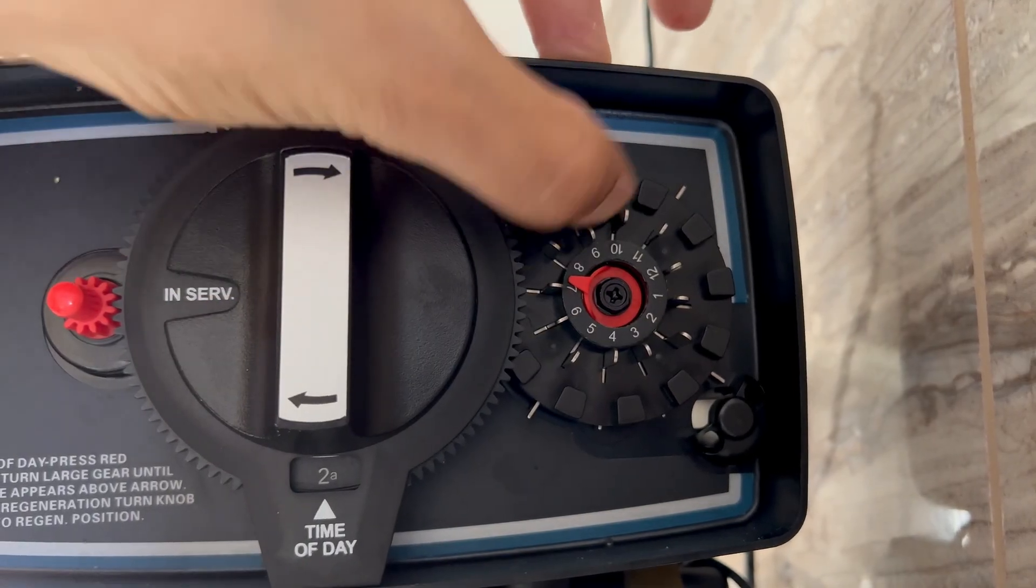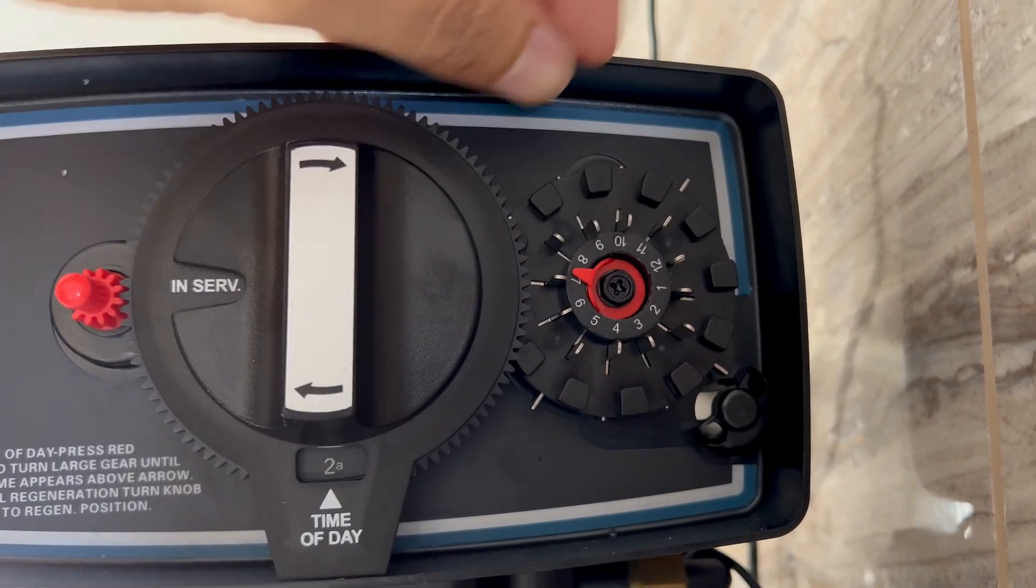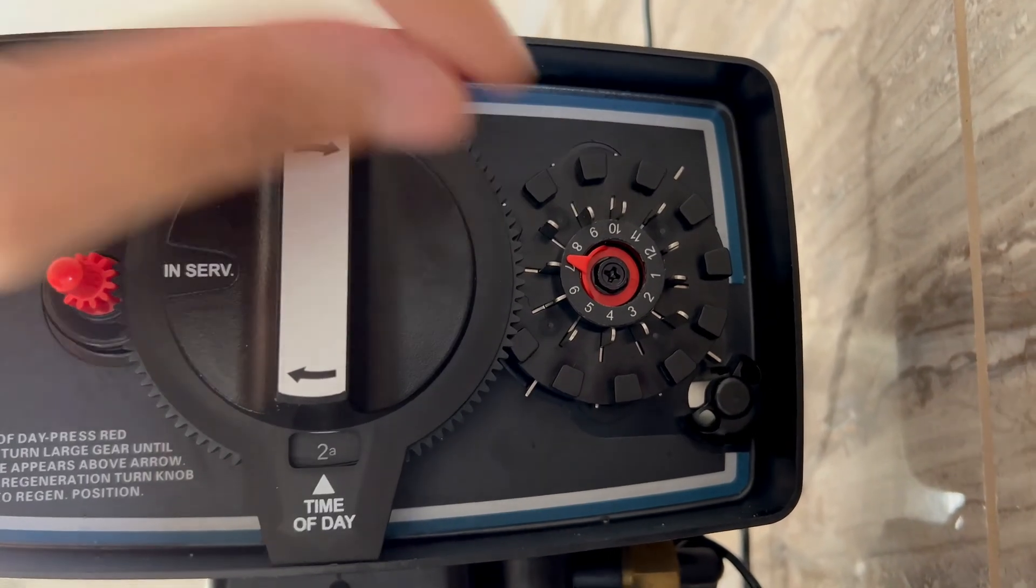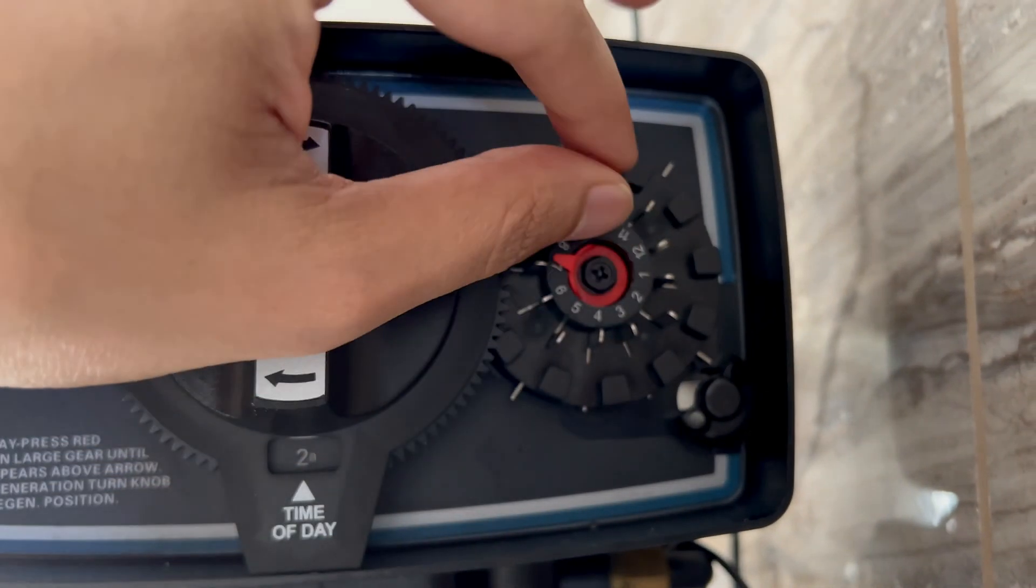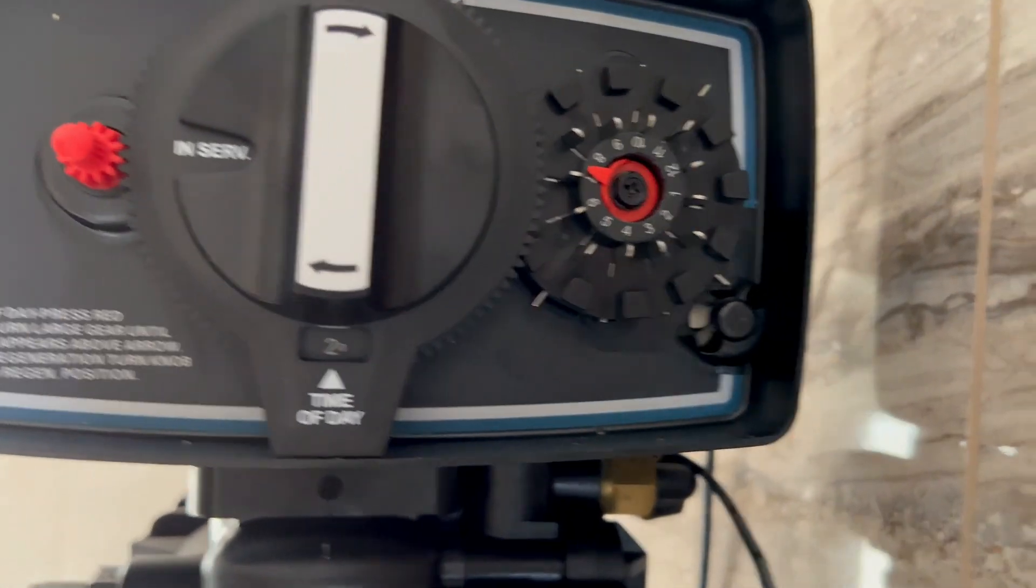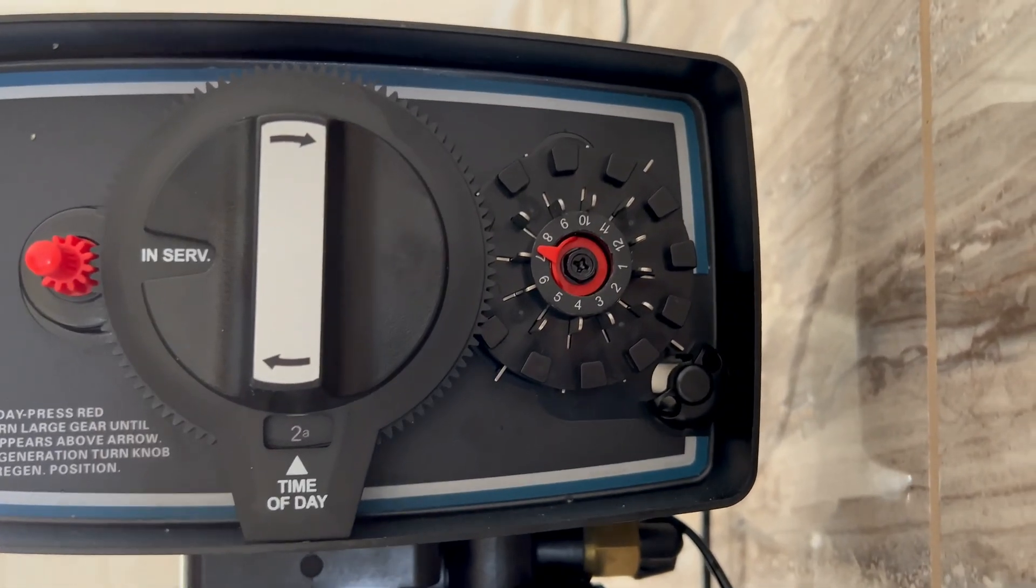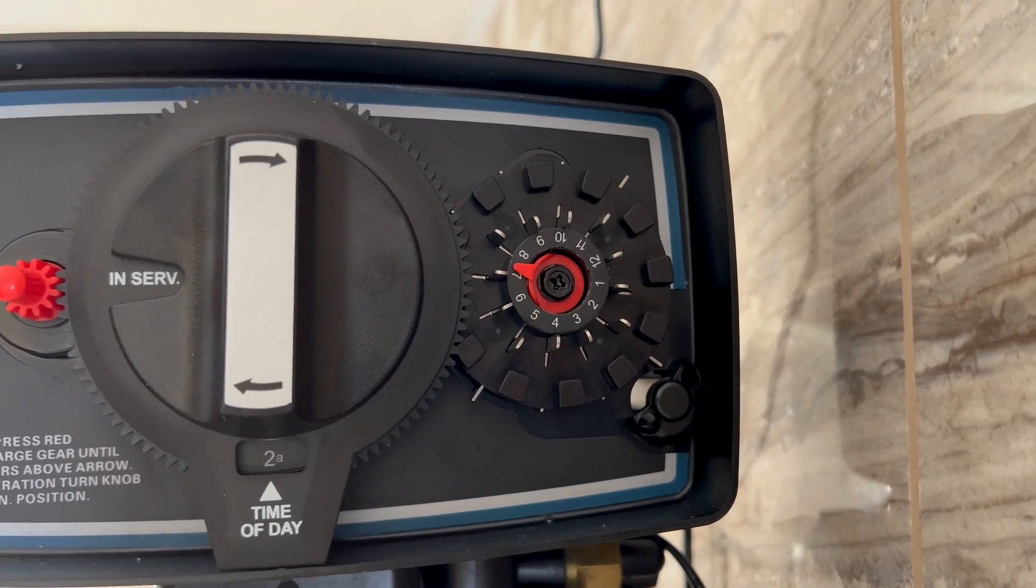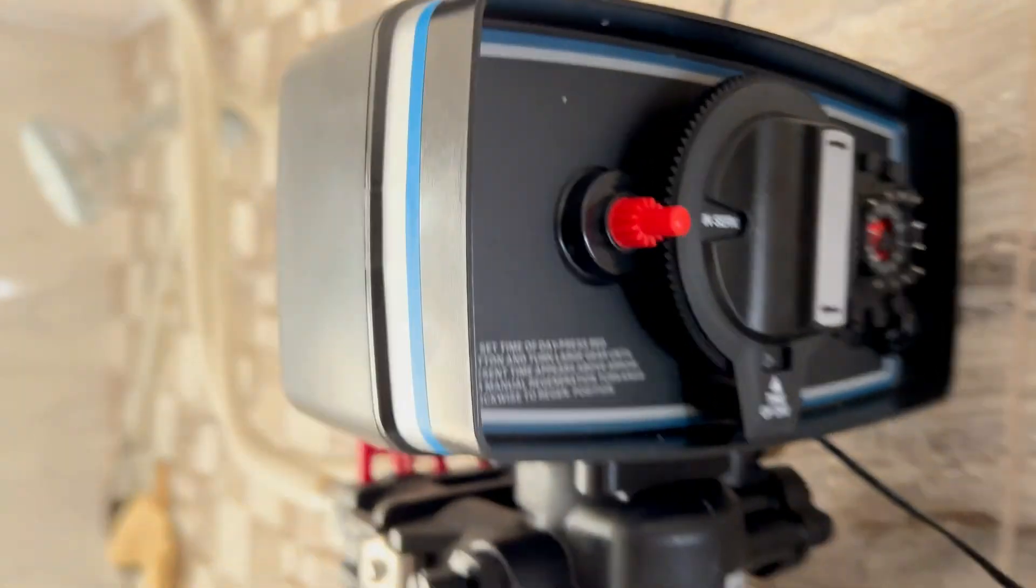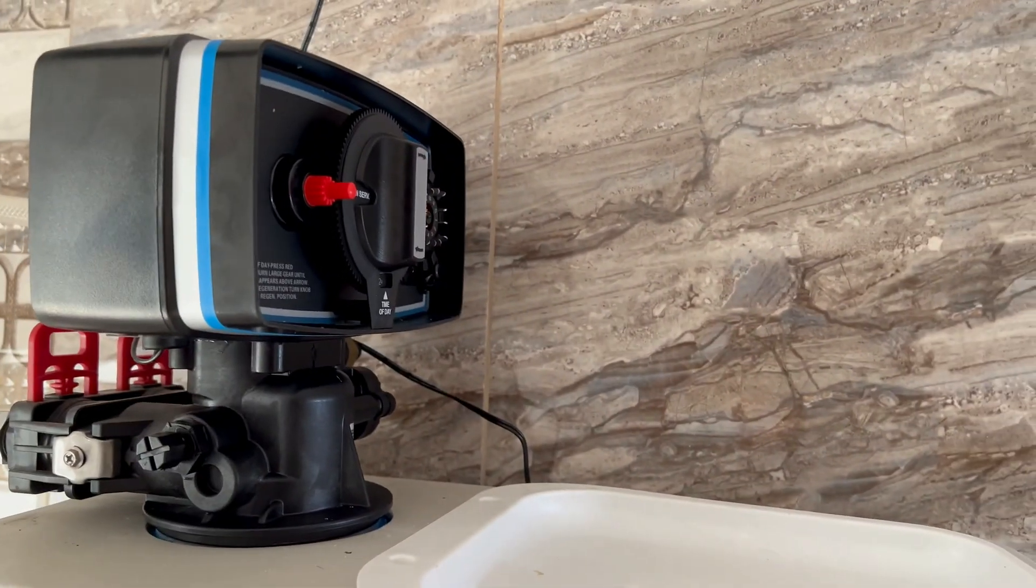The machine is designed to regenerate water at 2 a.m. based on its internal settings and it generally takes three and a half to four hours for the regeneration to complete and that's why it's good to have it at 2 a.m. but you can always change the time of the day to adjust it based on your schedule.